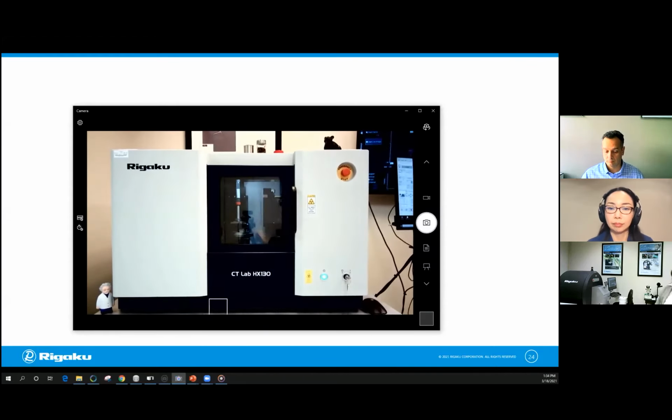Okay, so let's start with, I think you'll address this as well. Would it be helpful to tap down the sample to prevent potential movement during the scan? Yeah, or in fact, to wait some period of time. We will cover sample preparation in a sense, and you try to fix a small sample on the sample holder and make sure that it doesn't move during the scan.